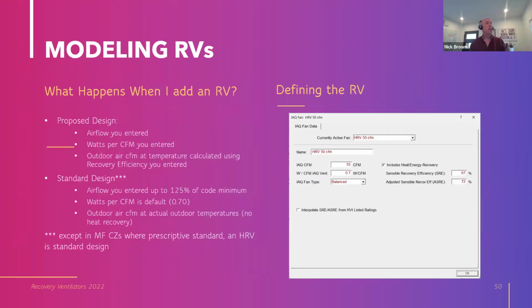When you add a recovery ventilator to a compliance model, the proposed design is the airflow, the watts per CFM, and recovery efficiency you entered. The standard design you're compared to for compliance is the same airflow you entered up to 125% of code minimum, at which point it stops increasing. So if your CFM is more than 25% above code minimum, you're going to get an increasing penalty because the standard design stays at 125% and you keep going up.